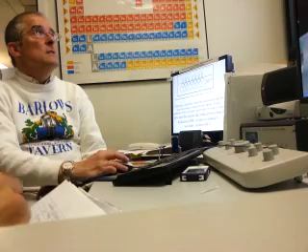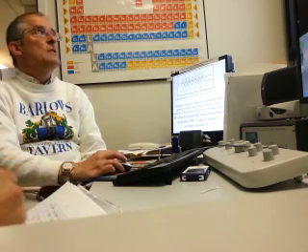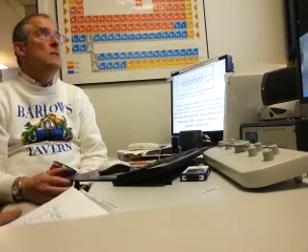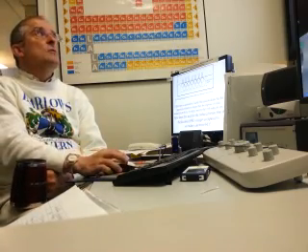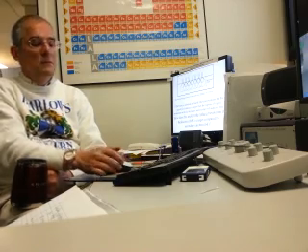As your penetration depth increases with increasing accelerating voltage, your Monte Carlo gets bigger, which means that what would be an acceptable Monte Carlo at lower accelerating voltage starts having overlaps at higher accelerating voltages, which means that it would affect your resolution. Say it means that it wouldn't affect resolution? It could. No, because you start getting overlaps, because remember your spot size is getting bigger and bigger as the Monte Carlo gets bigger.